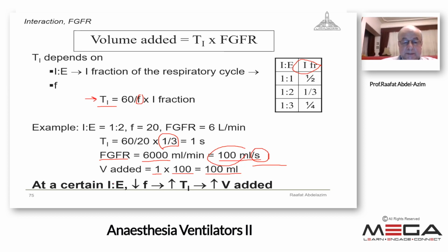At a certain I:E ratio, decreasing the frequency will lead to increasing the inspiratory time. For example, if the respiratory rate is 20 and the inspiratory time is 1 second, and we decrease the rate to only 10, this means the respiratory cycle is 60 divided by 10. The respiratory cycle time will be 6 seconds, divided into inspiration 2 seconds and expiration 4 seconds. So the inspiratory time would be 2 seconds.